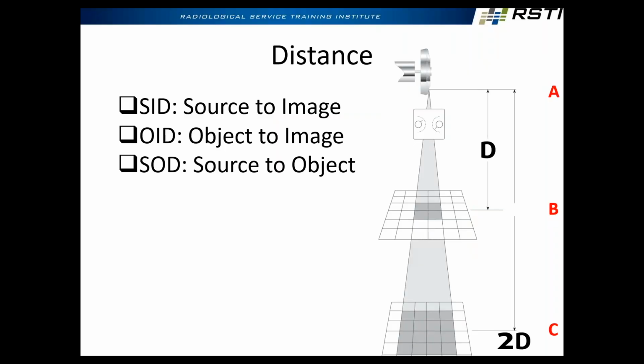SID, source image distance. So what does SID mean then? What's the source? The X-ray tube, the focal spot, right there. What's the image? The detector. Yep. So SID, source to image distance, is the distance in this picture from A to C. The source to image distance. OID is the object to image distance. Where's the object in this picture? B. The image is still C. So B to C is the OID.